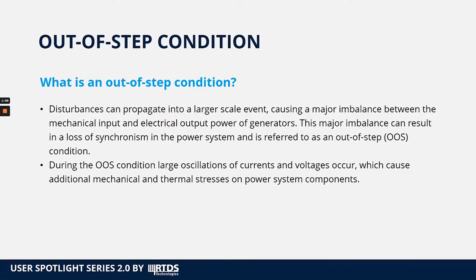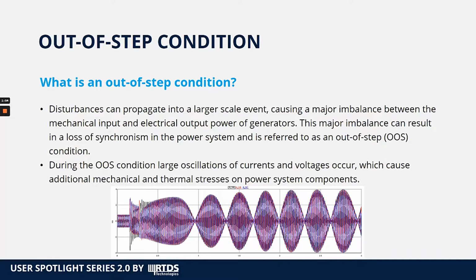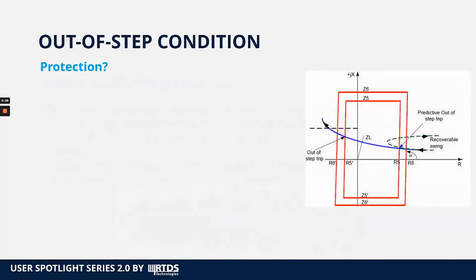As a demonstration of this, I have shown on this slide a current oscillation during an out-of-step condition from an RTDS simulation, where we can see that the oscillations in current values can become higher than the actual fault currents at the start of the event here on the picture. So therefore, we need to have some sort of protection installed in the network that can detect the out-of-step condition and react accordingly. Which leads me to the protection part of this presentation. So for out-of-step condition, what type of protection is conventionally used?